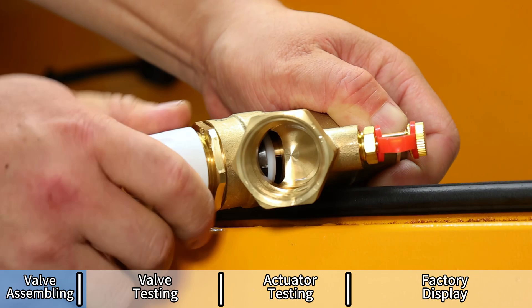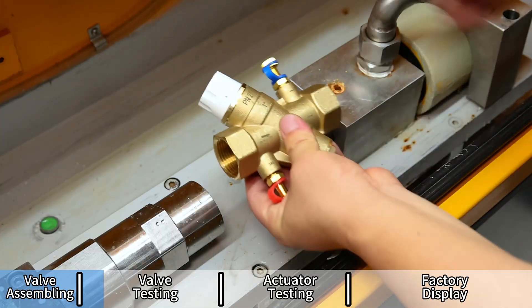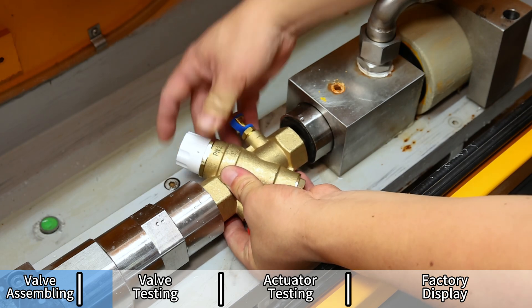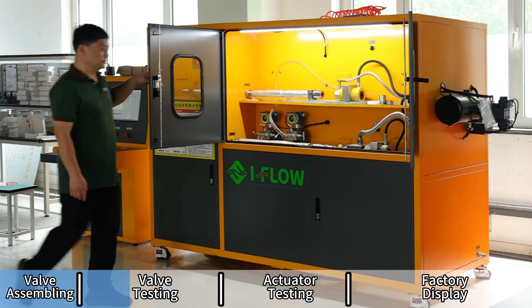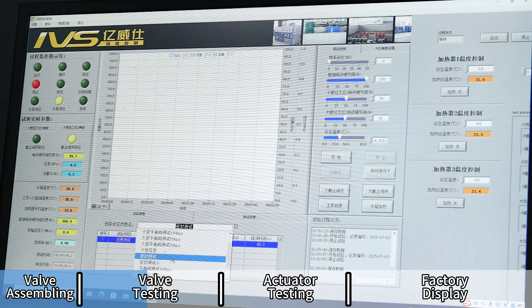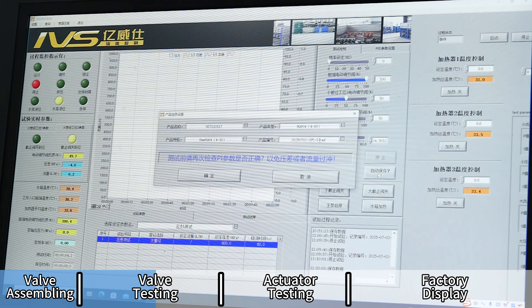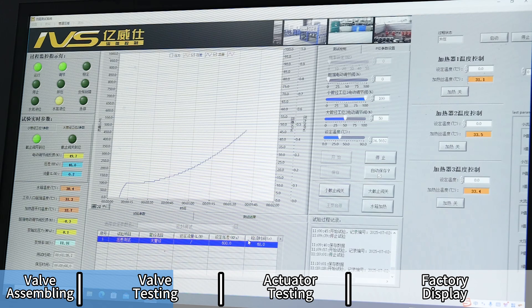In this segment, we perform a flow test to verify the PICV's pressure independent control accuracy. The valve is securely mounted on a test bench, and system parameters are set. Water flows through under varying pressure conditions, while sensors continuously monitor flow rate and pressure difference. Real-time data is displayed to check stability and sealing performance.